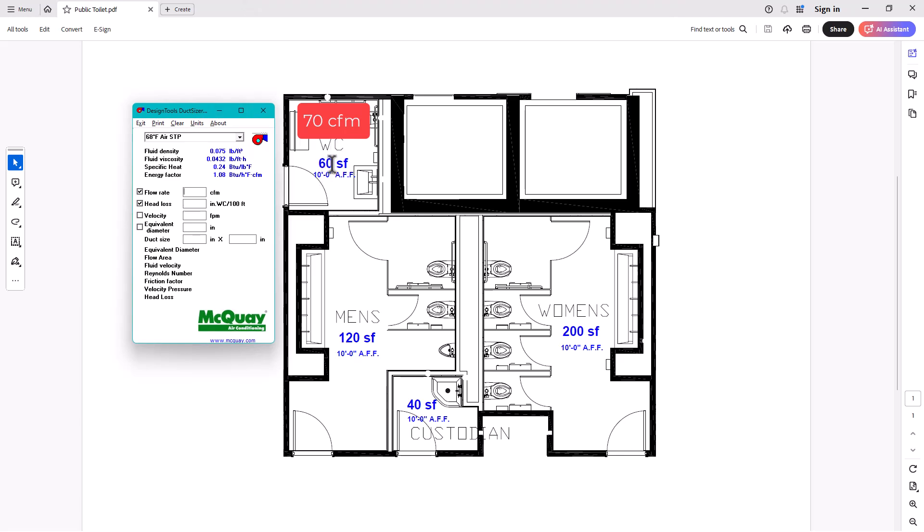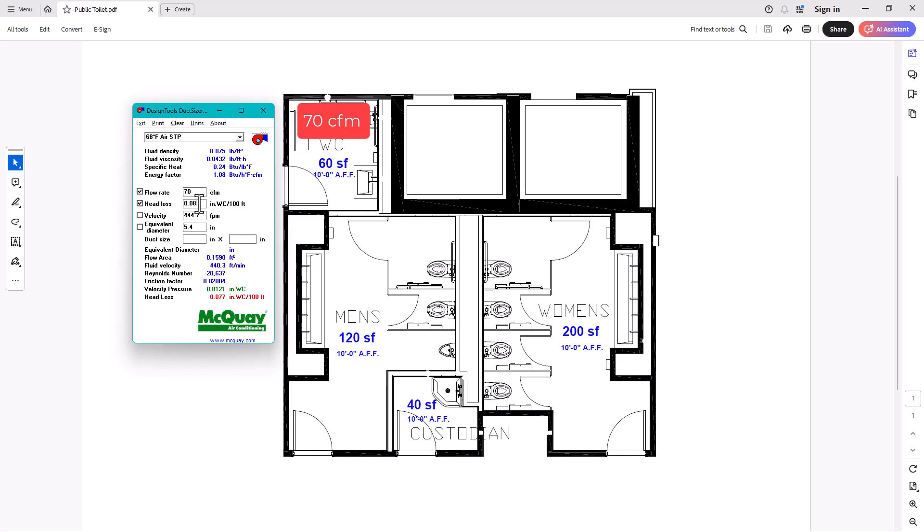Say that you need to connect it here with this. That depends on the designer, or depends if you have a roof. This could be all connected and go to the roof and put an exhaust fan. Or you can put, you don't have a roof. It's like, I mean, you have a roof, but this is a big building and you want to exhaust everything to the side wall, but then you put an inline fan and you need ductwork. We can be doing that later in another video. But overall, if you need to extract from this 70 CFM, what you're gonna put in here is the following. So you have in here, this is a quick tutorial. Put in here flow rate, 70 CFM. And then you're gonna put a friction rate of 0.08. There we go. Right. That's all you need. You need the CFM and the friction rate. That's all you need.